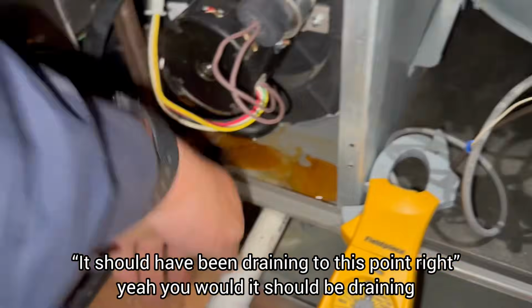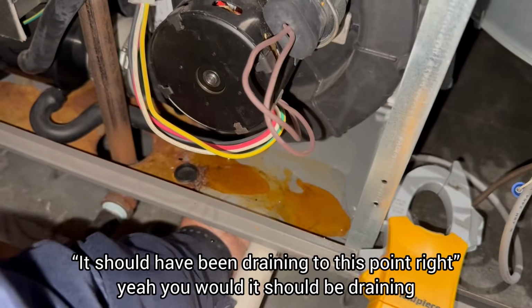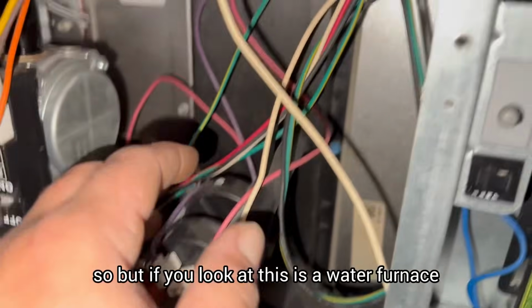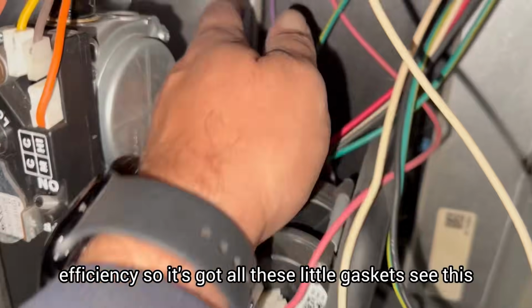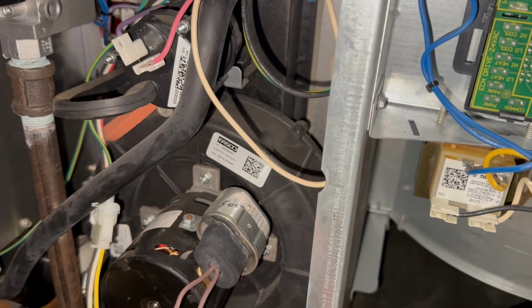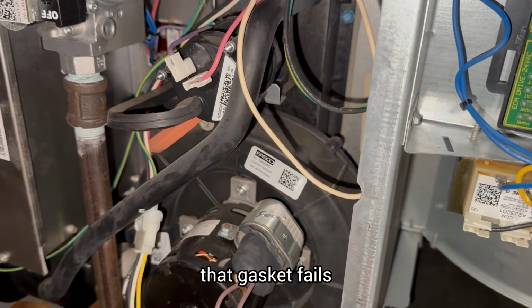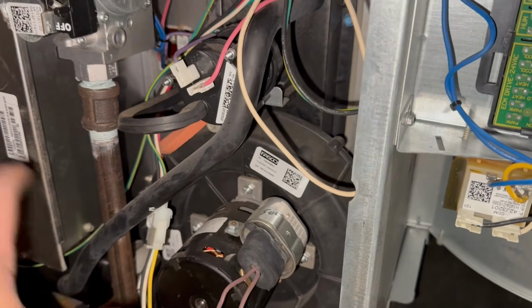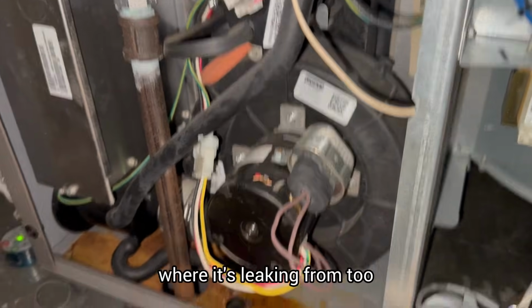So it should have been to this point, right? Yeah, it should be draining. But if you look at this, it's a water furnace - it's high efficiency, so it's got all these little gaskets. See this, right there at the bottom, what we find is that gasket failed. And what we have to do is take this motor off to bring it out, just to see where it's leaking from too.